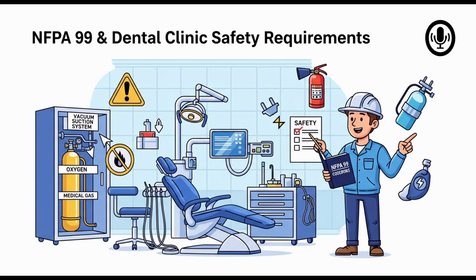The source did mention radiology, but it was in Annex A, which is the explanatory, non-mandatory part of the code. Item A.6.7.5.1.3 suggests that facilities might consider putting automatic battery-powered emergency lights in special procedure radiology rooms. Special procedure. Does that mean more than just routine dental x-rays? It sounds like it might imply more invasive procedures happening under imaging, but even then, it's just a recommendation in the annex, not a shall requirement in the main code body for standard dental x-ray spaces. So again, based strictly on this text, NFPA 99 doesn't seem to impose specific engineering requirements on typical dental radiology rooms beyond general electrical safety.